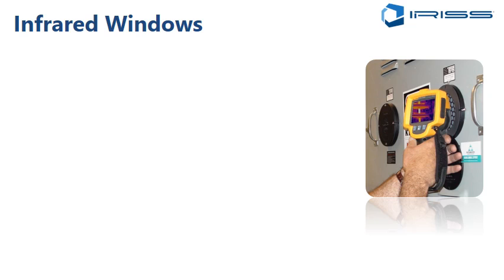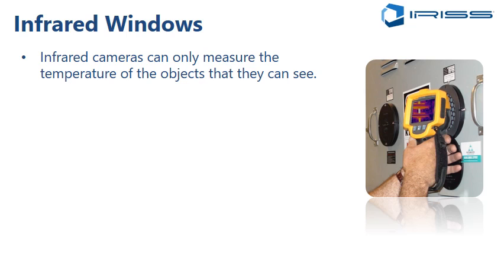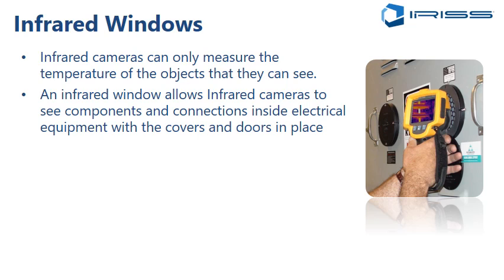So looking at an infrared window, you need to consider that infrared cameras can only measure the temperature of the objects that they can see, and infrared windows allow infrared cameras to see the components and connections inside an electrical cabinet with the covers and doors in place in what we class as an enclosed and guarded condition, which is the safest condition that we can use when trying to look inside the panels.